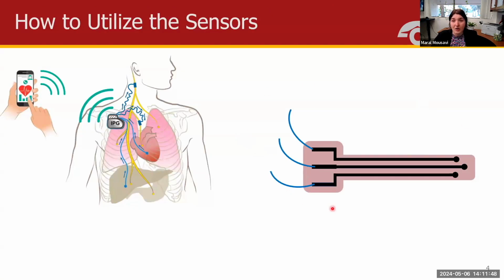So the sensors are thin film. The material that's used across these electrodes is Parylene. Parylene is resilient to moisture and oxygen permeation, so it does provide a really robust material, and it's also biocompatible. So all of these electrodes are thin film Parylene, depending on the module, whether this is acetylcholine pH or catecholamine. The thickness may be either 25 micron or closer to 100 micron thick.